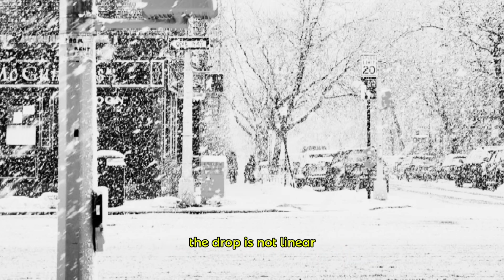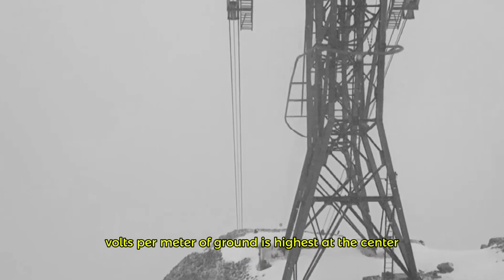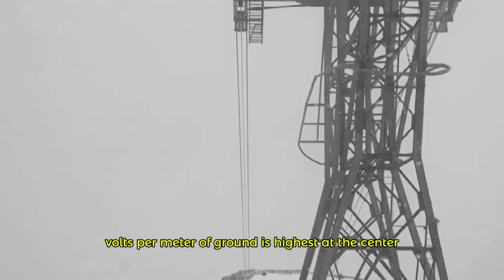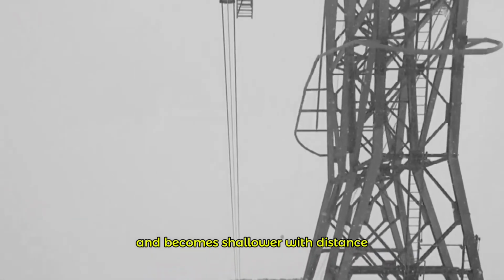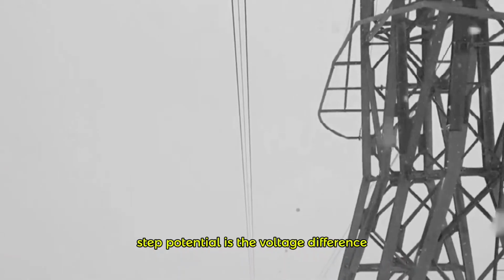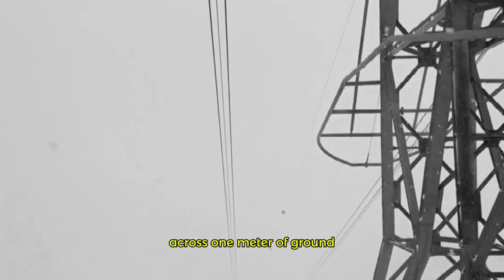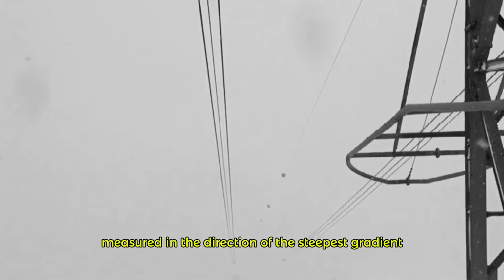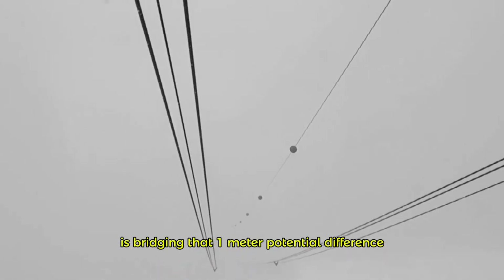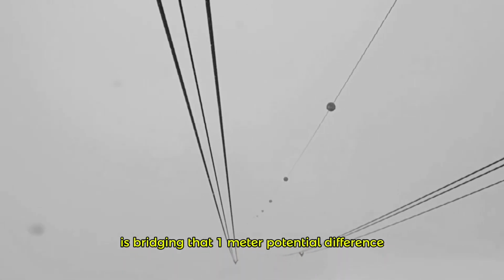The drop is not linear. Voltage falls steeply in the first few meters and then flattens. The gradient, volts per meter of ground, is highest at the center and becomes shallower with distance. Step potential is the voltage difference across 1 meter of ground measured in the direction of the steepest gradient. A person standing with one foot 20 meters from the contact point and the other foot 21 meters away is bridging that 1 meter potential difference.